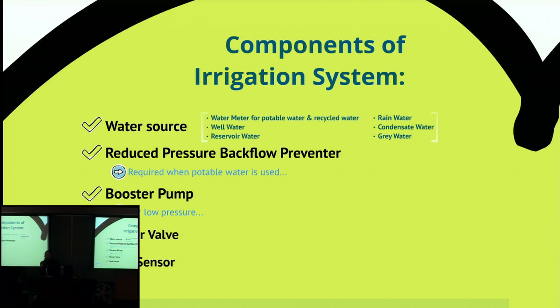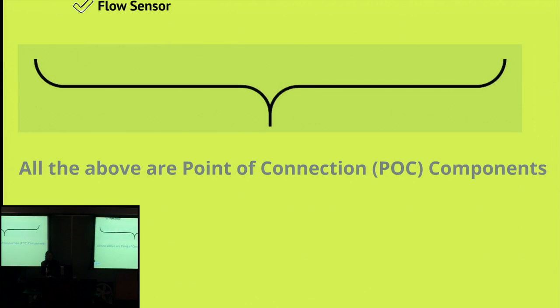And the reason we have that in there is today, because of the water ordinances, more of the cities are requiring that you use smart controllers. And along with the smart controllers come the master valve and the flow sensor. So all of the above are POC, or point of connection components. And that's when you're out in the field, that's where you're going to start looking at things.